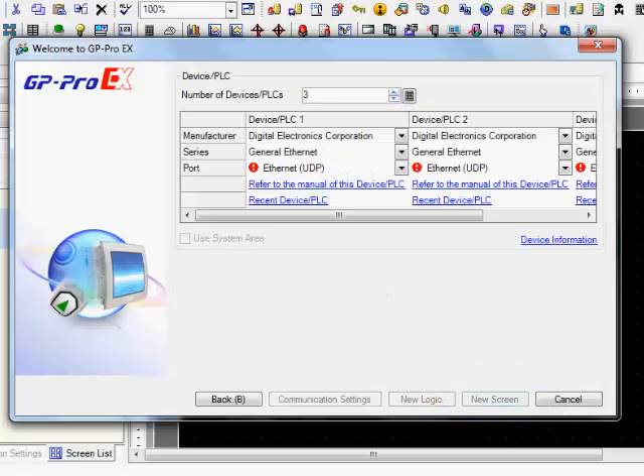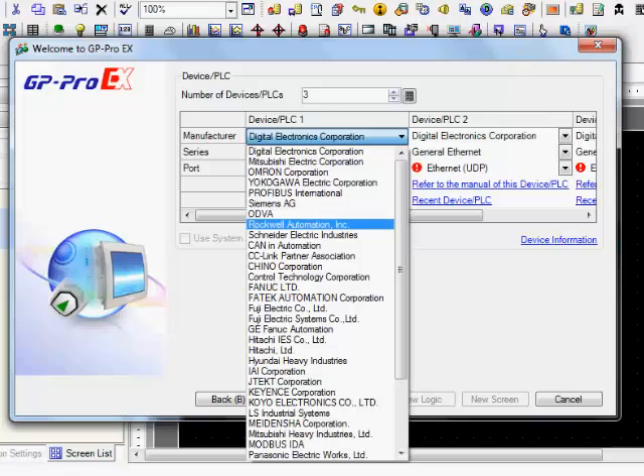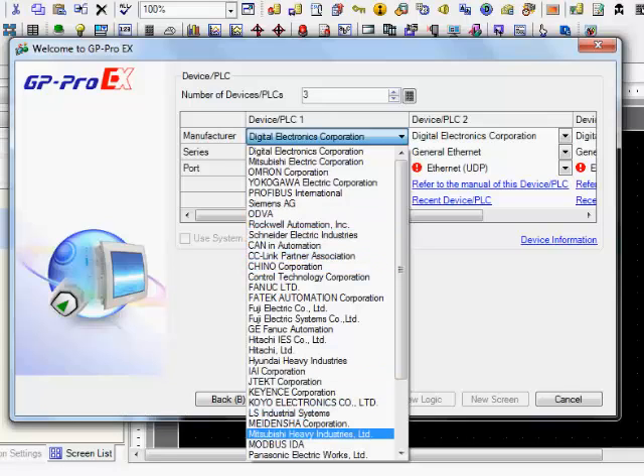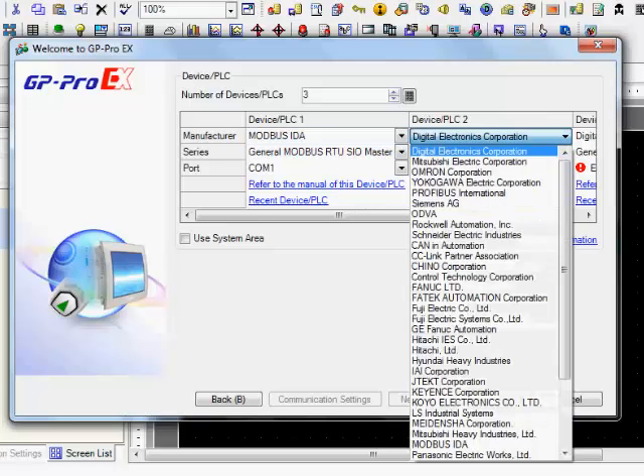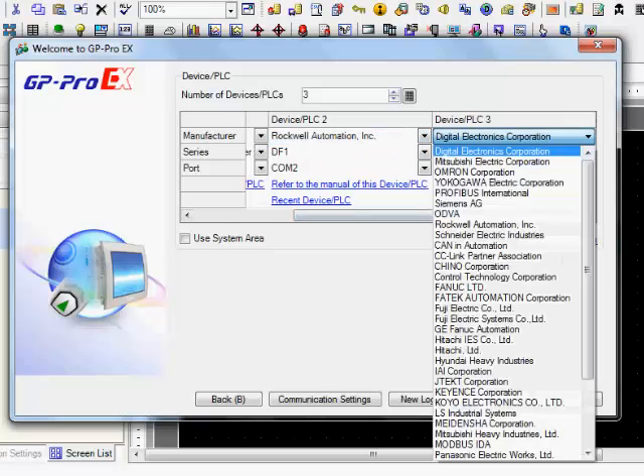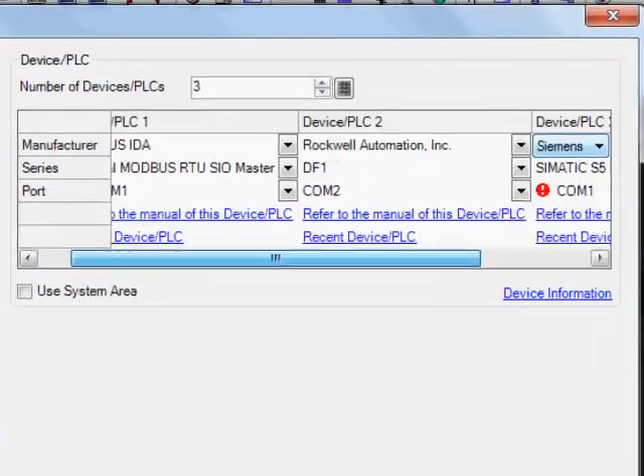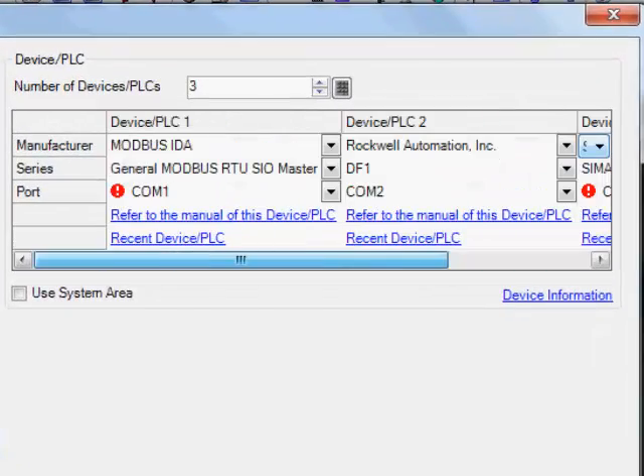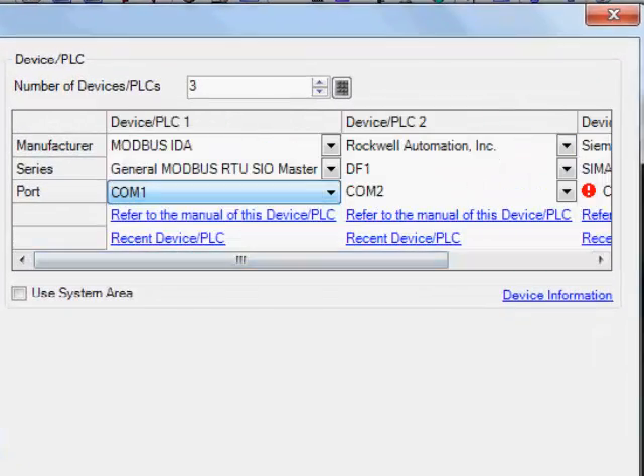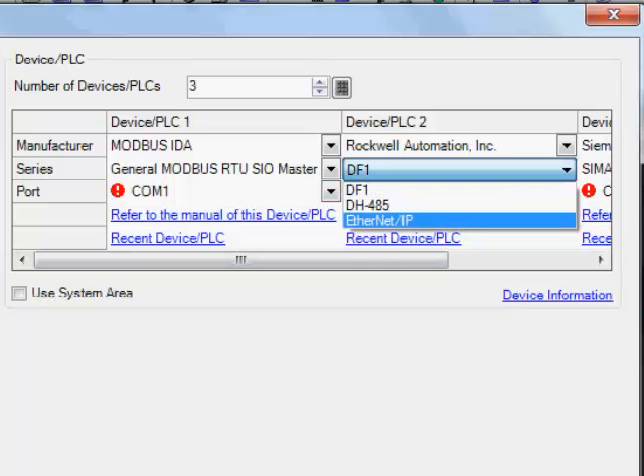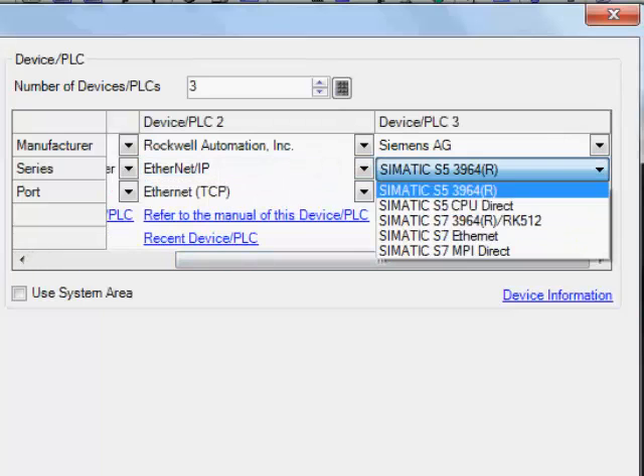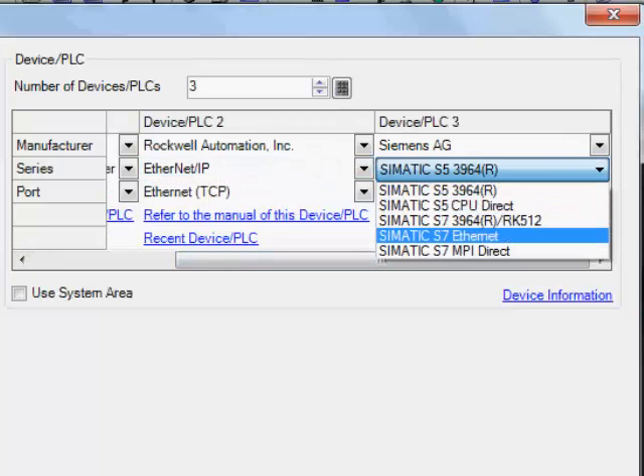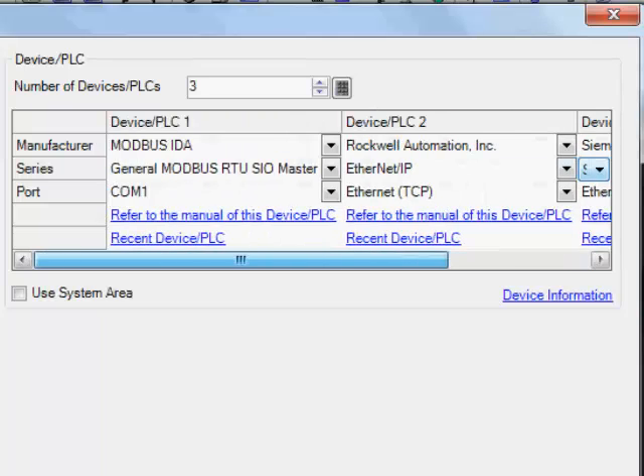We're going to actually select three different types of PLCs, this is three different drivers to us. My first one I'm going to select a Modbus, the second one I'll select as a Rockwell, and a third one as a Siemens. You can see how I've entered those all in. For the Modbus I'll go ahead and use that as a COM1, the Rockwell I'll go ahead and select that as an Ethernet IP, and a Siemens I'll go ahead and also make that an Ethernet driver.